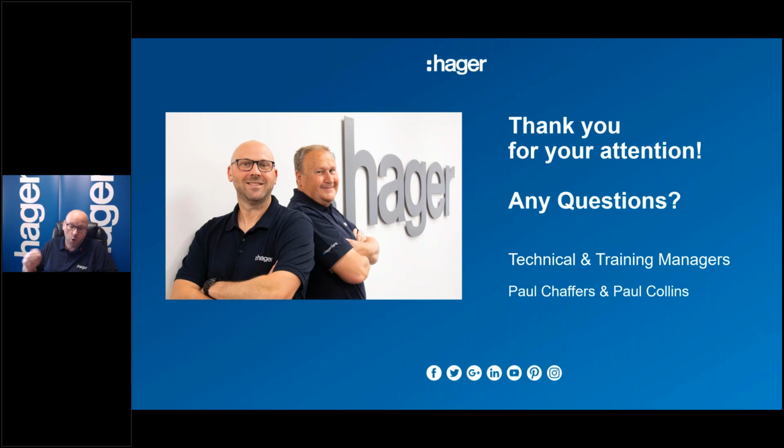So what we would say is you're absolutely fine to replace that broken socket, and if you use a Minor Works form, you could recommend the upgrade to a Type A device. All clients are different, as you know. Some clients will trust and value your opinion, in which case you might want to say, look, I'm going to change your socket, and we should be updating your device now.